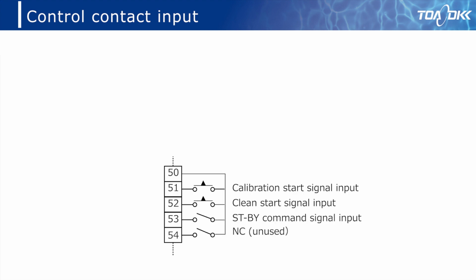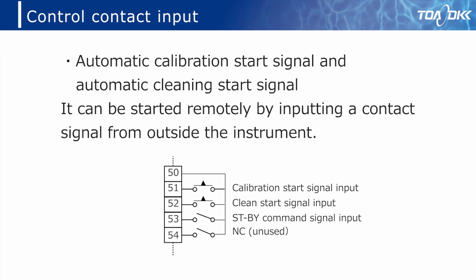This section explains control contact input. A closed contact input is the function to start the instrument. Next, we will explain the automatic calibration start signal and the automatic clean start signal. Cleaning and calibration are performed at the set cycle. Besides, they can be started remotely from outside the instrument by inputting a contact signal. Calibration and cleaning are started by a closed contact input of 100 millisecond width or more.